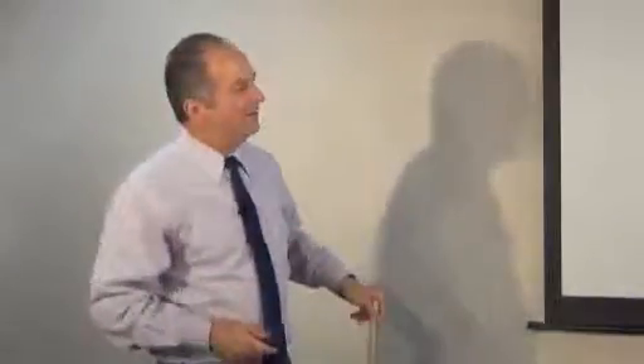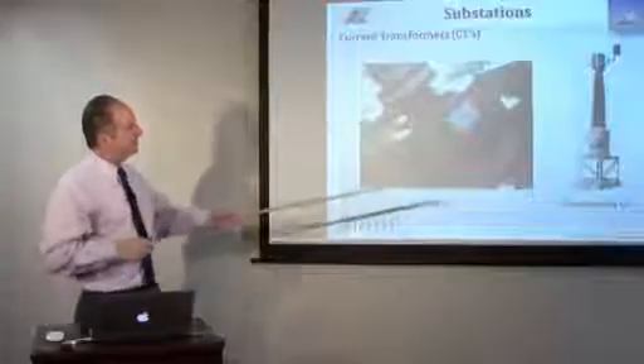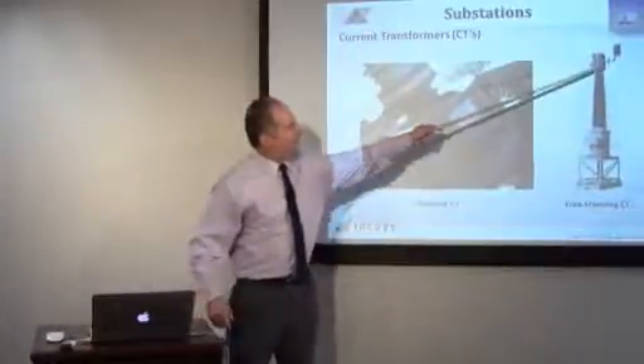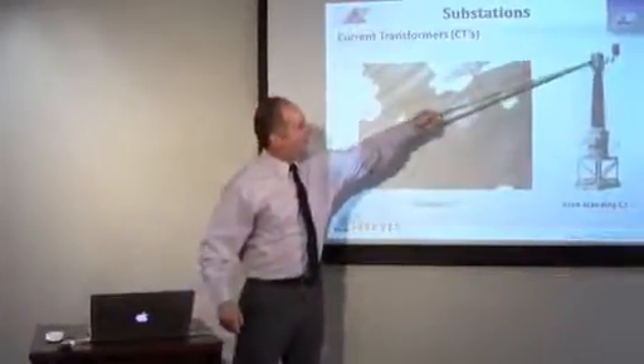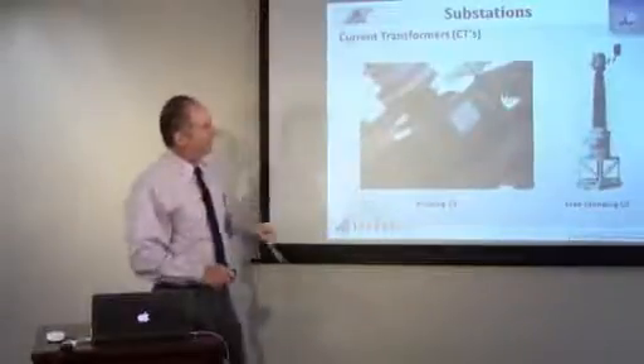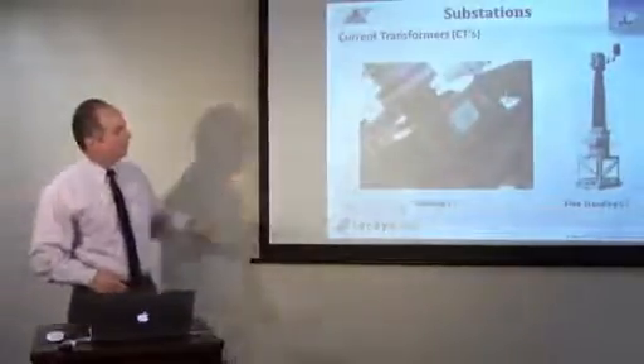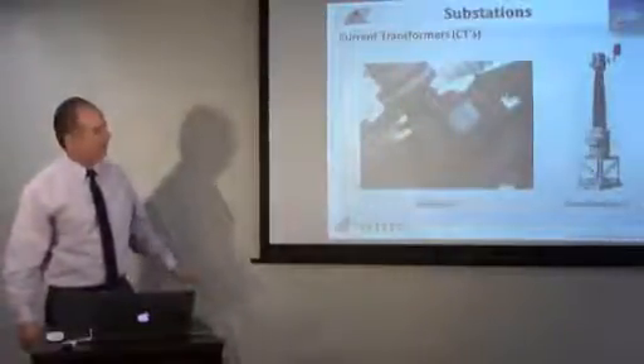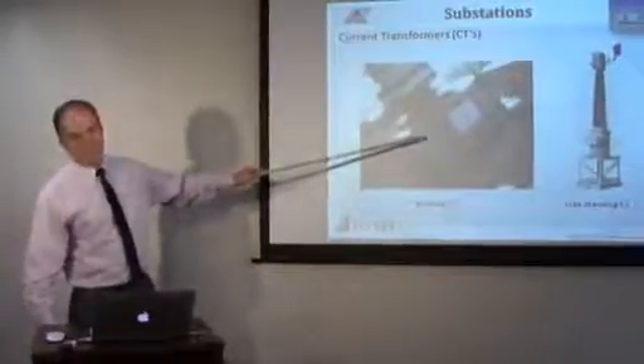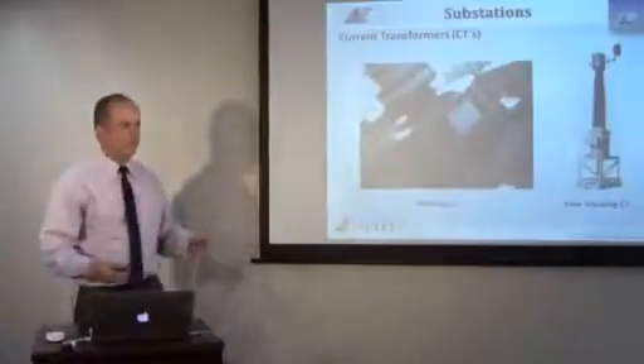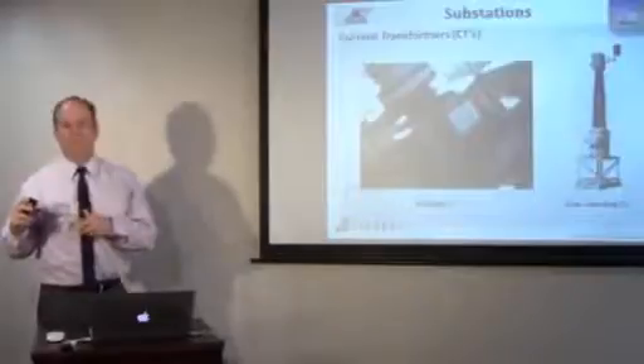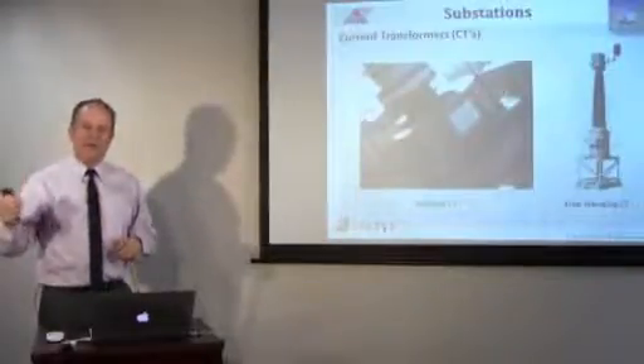Okay, that's a CT. Sometimes you have to have a standalone CT where current goes through the top here and you're just measuring the magnetic field and bringing that into the substation. That's a 500 kV freestanding CT. This is a donut CT. Smaller ones are used in metering. If you were an industrial customer and you had a small CT, your meter on the side of the building is operating on a much lower current than the real current that's flowing through the power line.